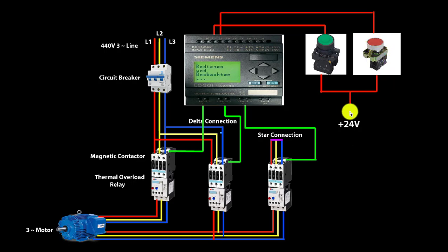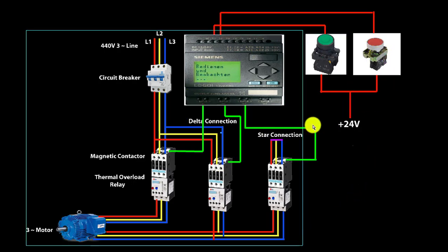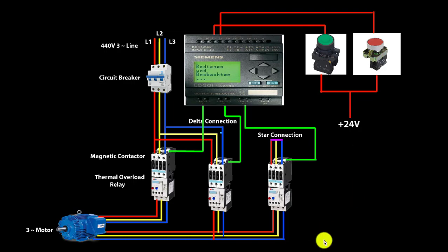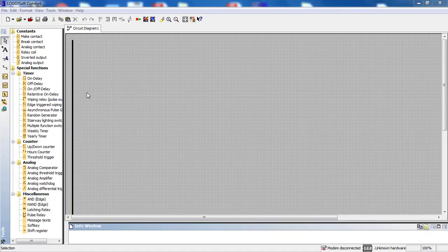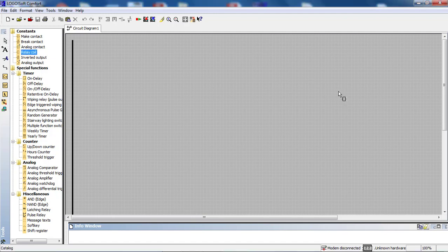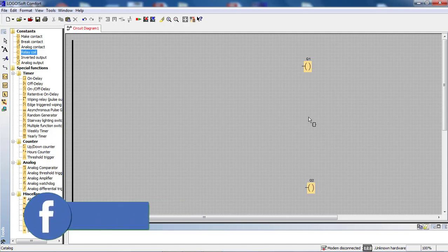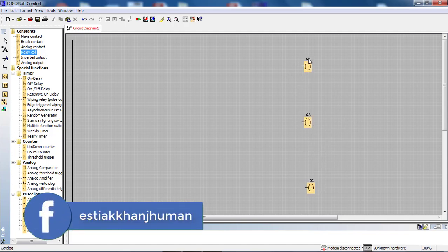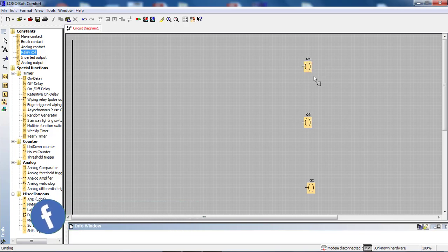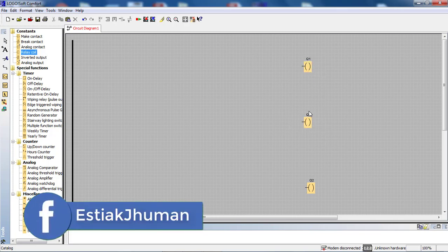This is the circuit diagram. Now we start the ladder diagram. If we have star-delta conversion, we have a total of 3 magnetic contactors and 3 outputs. So we have Q1, Q2, and Q3. Q1 is the main magnetic contactor, Q3 is the star connection, and Q2 is the delta connection.